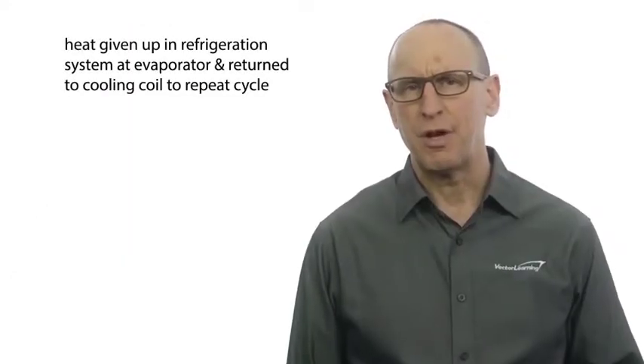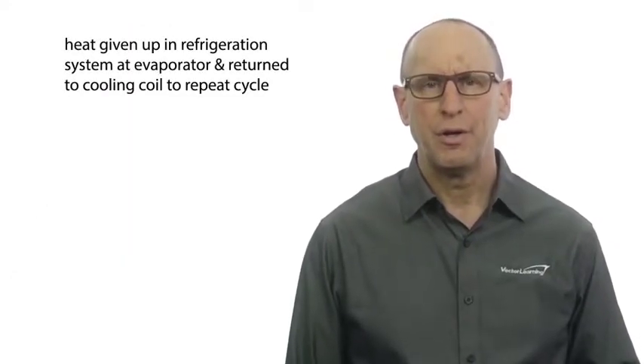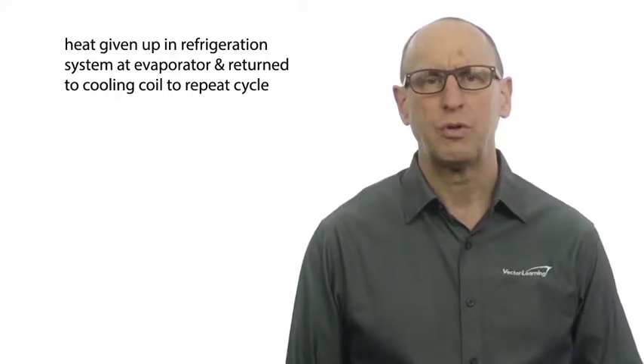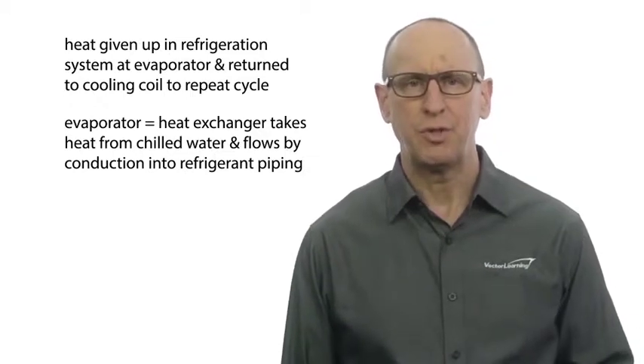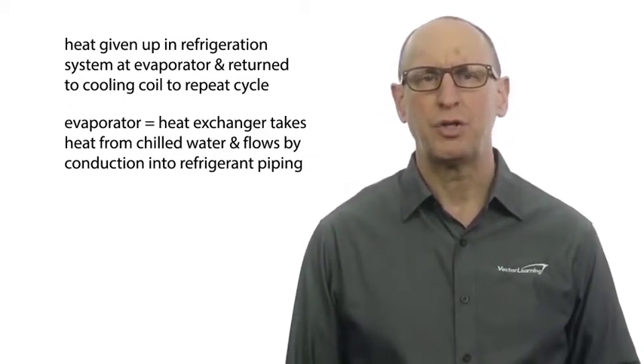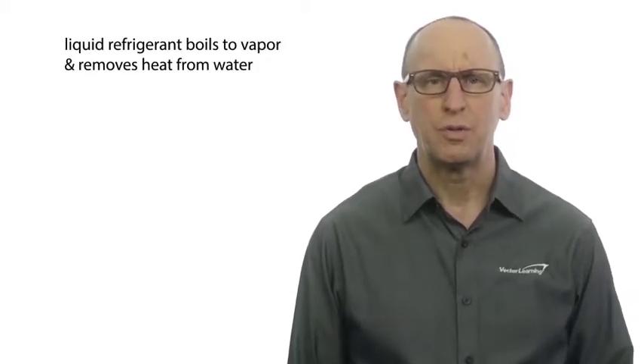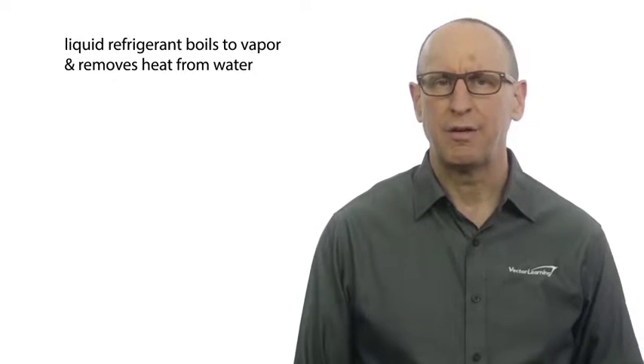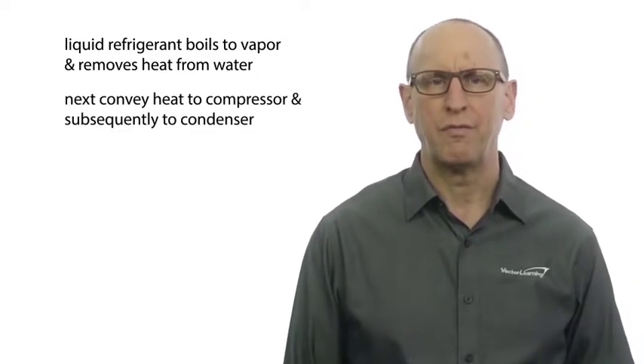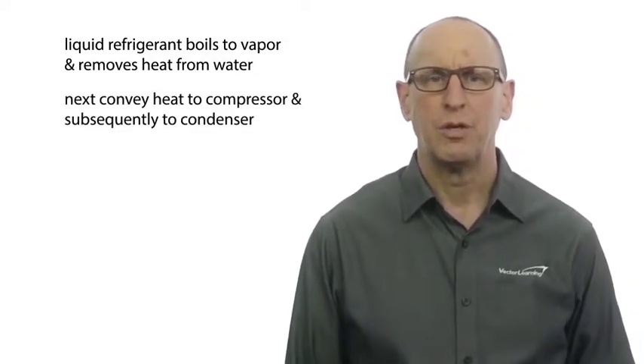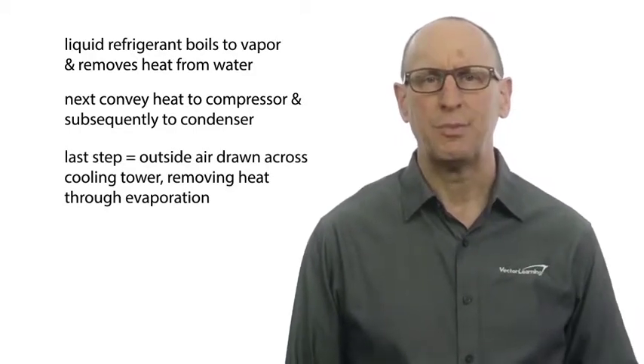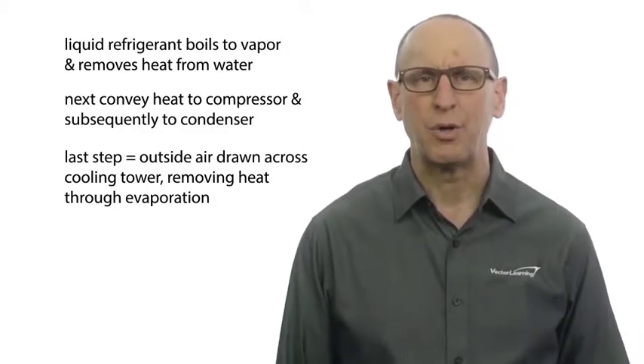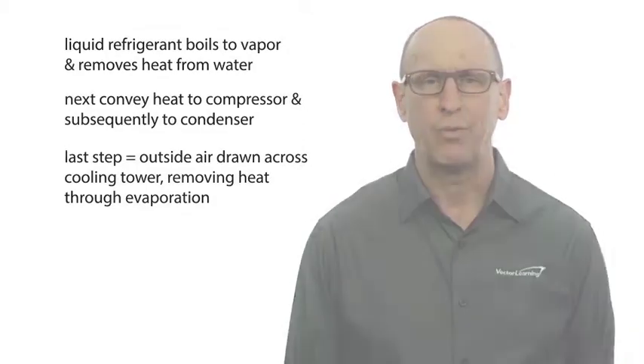The heat is given up in the refrigeration system at the evaporator and returned to the cooling coil to repeat the cycle. The evaporator is a heat exchanger that takes heat from the chilled water and then flows by conduction into refrigerant piping. The liquid refrigerant in the tubes boils to a vapor and removes the heat from the water to convey the heat to the compressor and subsequently to the condenser. The last step is for outside air to be drawn across a cooling tower, thus removing the heat from the water through evaporation.